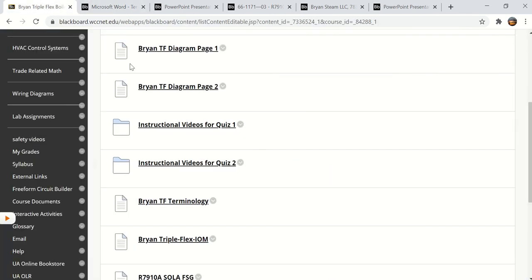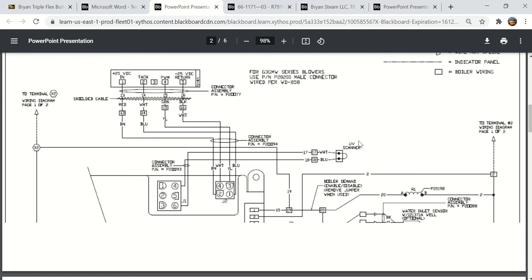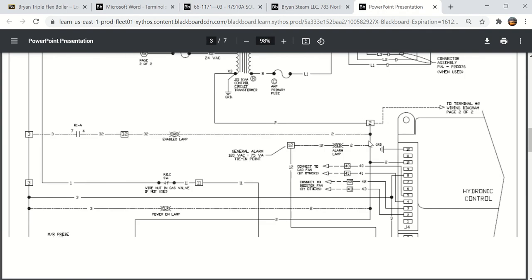So going back to the diagram, on sheet 2, page 2 of the diagram, which is the right hand half of the diagram we've been working with, here's where you'll see connector J1 and terminals 4 and 6. This is where the actual scanner that you just looked at plugs in. There's the UV scanner. So getting back to our diagram here, now that we know power going in on J48 is for the ultraviolet scanner, we assume that since they wired that, this boiler is using an ultraviolet scanner, and we did prove that by looking at the right hand sheet of the wiring diagram, and you saw where the ultraviolet scanner plugs in.